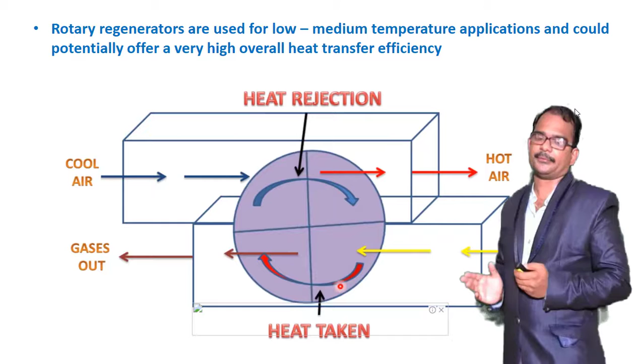Now, the heat absorbed from the exhaust gases at the bottom part moves to the top part, where you pass cold air from the top duct, or cold duct. This cool air takes the heat stored in the heat wheel and becomes hot air. So at the bottom duct, heat is absorbed by the heat wheel, and at the top duct, the heat is rejected by the heat wheel to the cold air, so the cold air becomes hot air. That is how the heat wheel works.